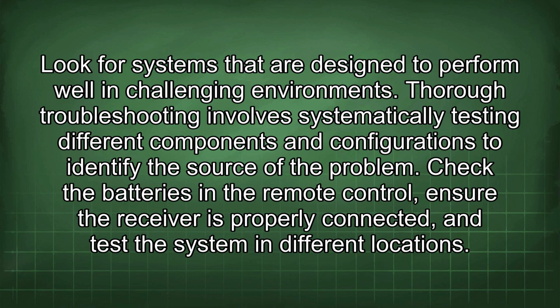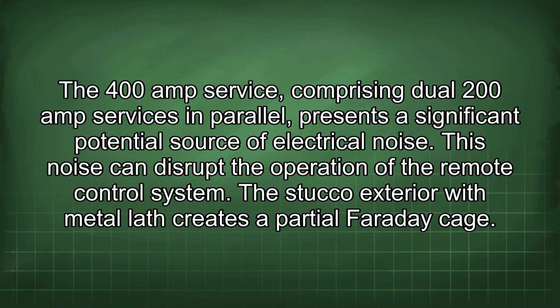Thorough troubleshooting involves systematically testing different components and configurations to identify the source of the problem. Check the batteries in the remote control, ensure the receiver is properly connected, and test the system in different locations. The 400 amp service, comprising dual 200 amp services in parallel, presents a significant potential source of electrical noise. This noise can disrupt the operation of the remote control system.